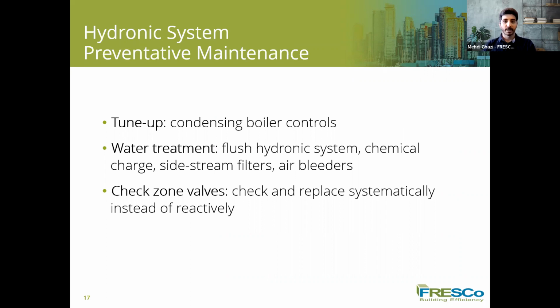So for our hydronic system, these days it's quite common to use condensing boilers, but even when we have condensing boilers installed, it doesn't necessarily mean that they are working in an efficient condition. So this is something we need to make sure of: whether the outdoor reset temperature sensor is actually connected or not, and we need to check if the boiler temperature goes down as it gets warmer out. That could be a sign that the outdoor temperature reset system of the condensing boiler is working, because that is a feature of the condensing boiler, and that is one of the reasons that we are installing them these days actually.